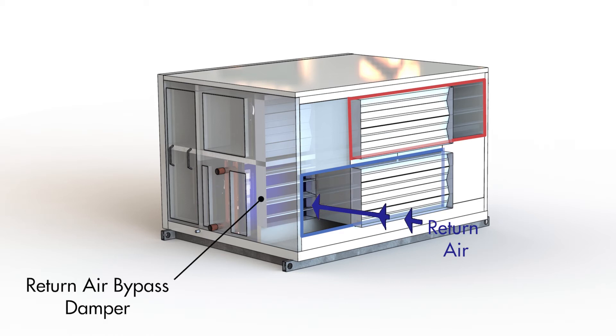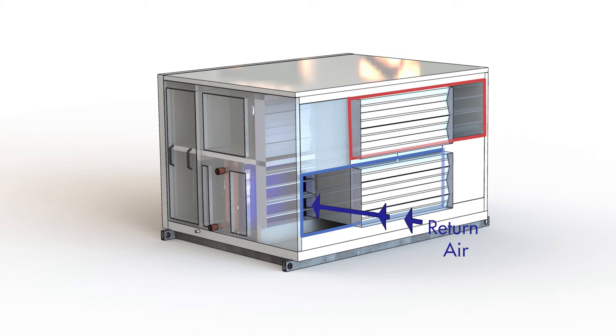Note that the return air bypass damper is the lower damper shown here in the bypass section. If you can recall from our previous video, the upper damper here is the economy cycle mode damper, which instead allows the return air to flow to exhaust when it is open. As opposed to economy cycle mode, which is either on or off, return air bypass mode can modulate.